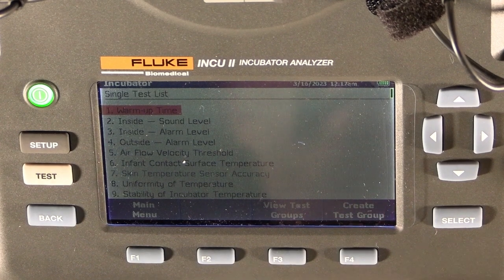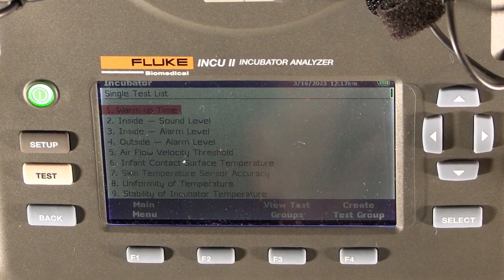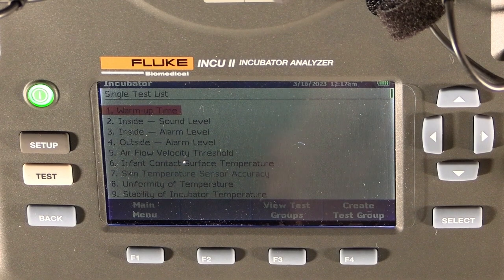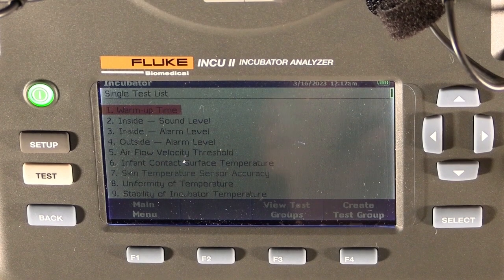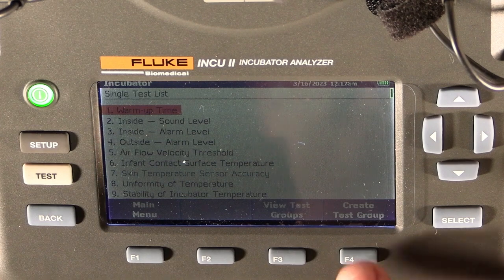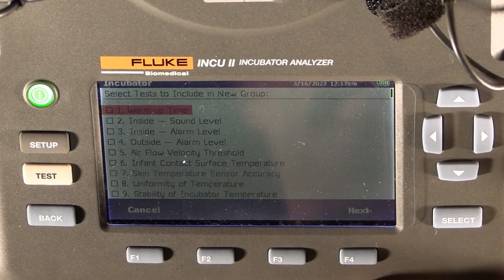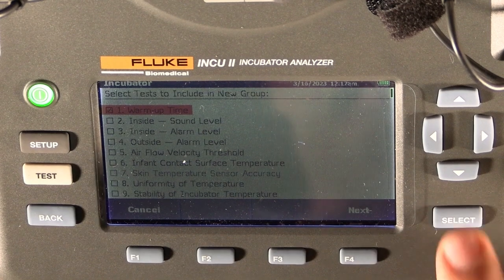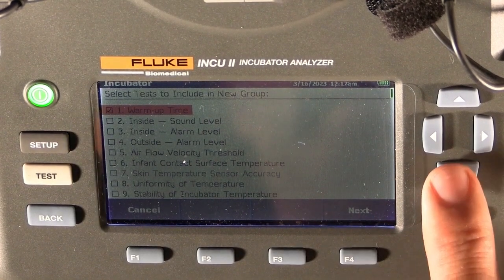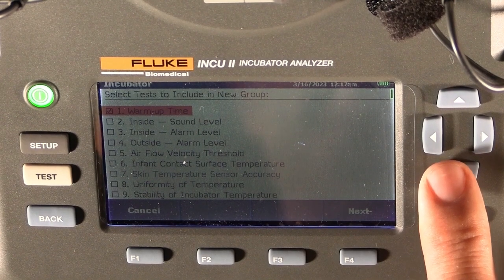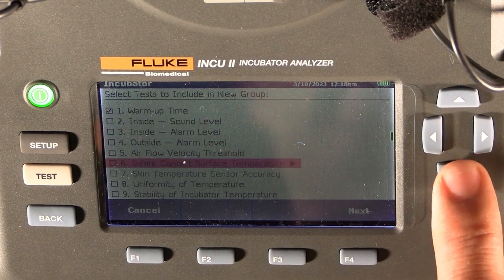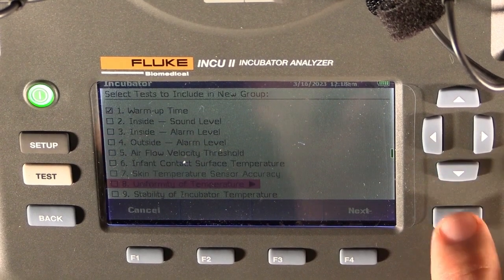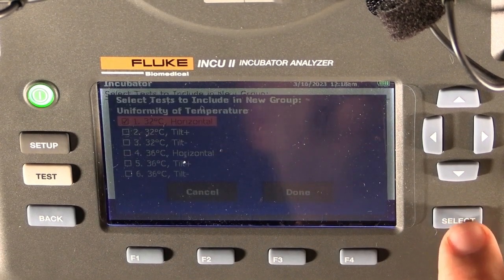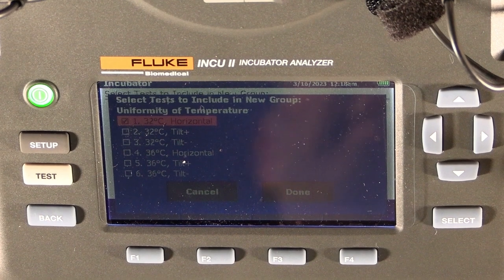Now, a lot of these tests will cause you to switch off the system, place your sensors in place, switch on the system, and wait half an hour to an hour for the unit to reach a stable temperature before you can do any measurements. Now, in order to save time, you can actually go and create a group of tests. Like for instance, the warm-up time. I can say I want to select the warm-up time, but while it's testing the warm-up time, with the configuration of probes needed for warm-up time, I might just as well also do the uniformity temperature test, and that one, the uniformity you need to do at 32 and 36 degrees.